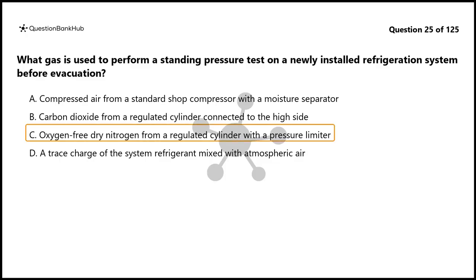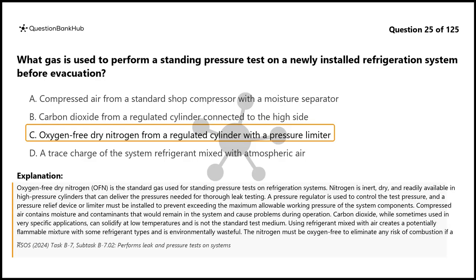The correct answer is C. Oxygen-free dry nitrogen, OFN, is the standard gas used for standing pressure tests on refrigeration systems. Nitrogen is inert, dry, and readily available in high-pressure cylinders that can deliver the pressures needed for thorough leak testing. A pressure regulator is used to control the test pressure, and a pressure relief device or limiter must be installed to prevent exceeding the maximum allowable working pressure of the system components.